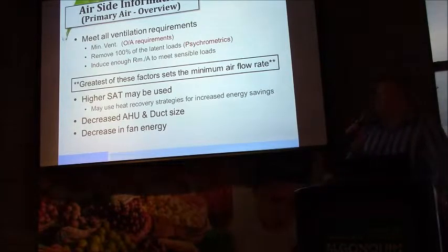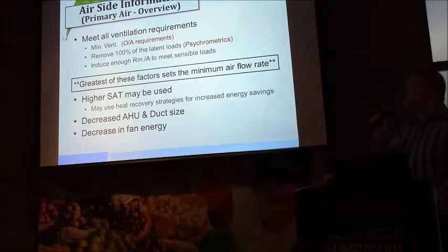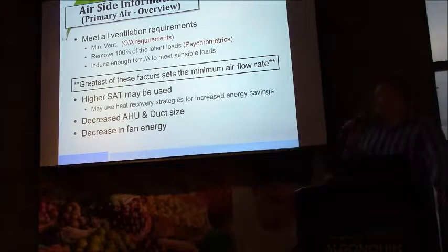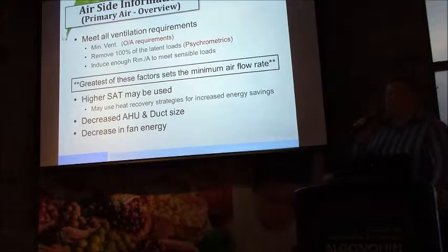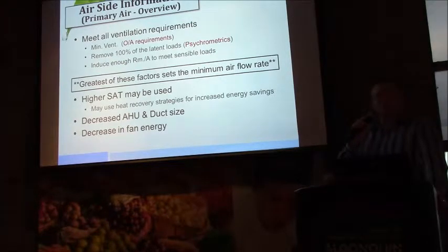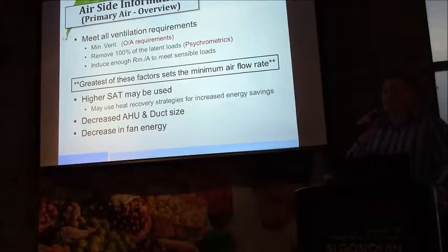And a case whereby you may find that you can meet the minimum ventilation with no problem in terms of your psychrometric load analysis and remove 100% of the latent load may be a transitional space in a corridor near some exterior glazing. Don't have a lot of requirement for dehumidification. There's very minimal ventilation load, but there's a tremendous sensible load. And so it's quite appropriate, or it's a space that could be considered very suitable for an active beam, given that if our goal is to minimize the primary air that's consumed, with the proper selection, we could see a beam in that space that could yield 1 ton of sensible cooling, or 12,000 BTUs of sensible cooling, for as little as 100 CFM of primary air. And that would be considered a very efficient airside delivery system for delivering 1 ton of sensible cooling, or 12,000 BTUs. And the greatest of these sets the minimum primary air.